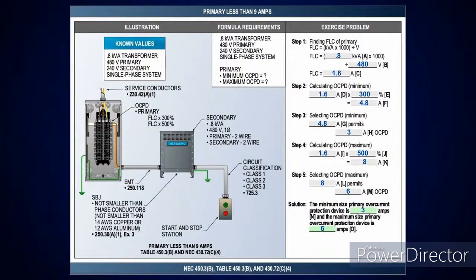Now, the next one is where I'm going to be dealing with a current that's less than 9 amperes. Looking in the illustration, I have a 0.8 kVA transformer and a 480 volt single phase. So I'm going to take 0.8 times 1,000, which is 800, and divide it by 480 volts, which gives me 1.6 amps.